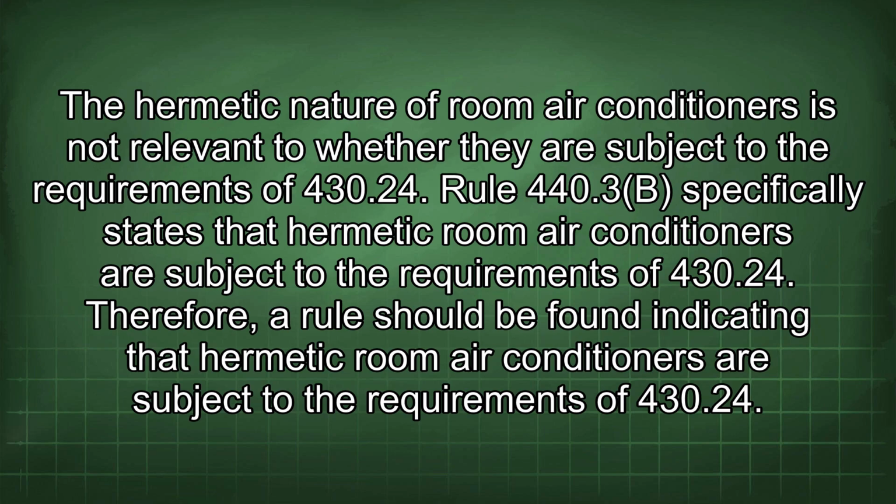Rule 440.3(B) specifically states that hermetic room air conditioners are subject to the requirements of 430.24. Therefore, a rule should be found indicating that hermetic room air conditioners are subject to the requirements of 430.24.